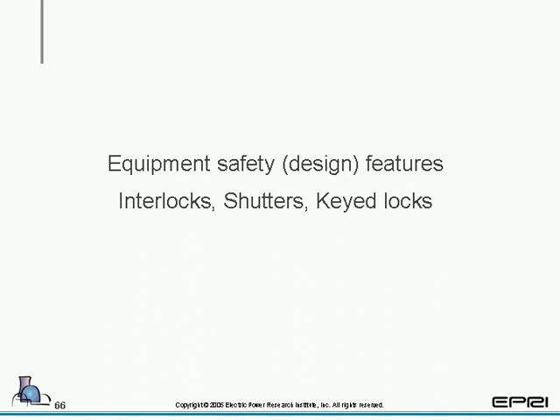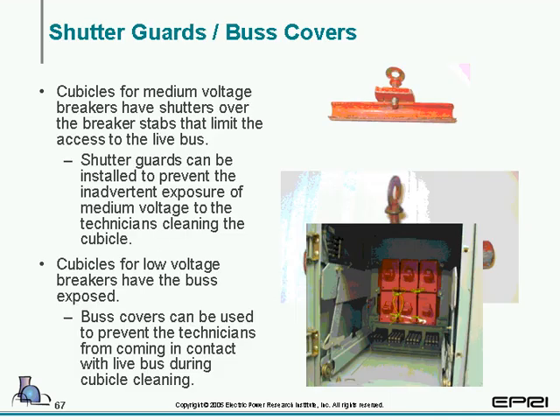Now we're going to talk a little bit about safety features such as interlock shutters and keyed locks. On medium voltage circuit breakers, typically what you have is a thing called shutters. Or I think most, if not all, medium voltage breakers have shutters. When the breaker is lowered and racked out, these shutters close to prevent inadvertent exposure of personnel to any energized stuff.